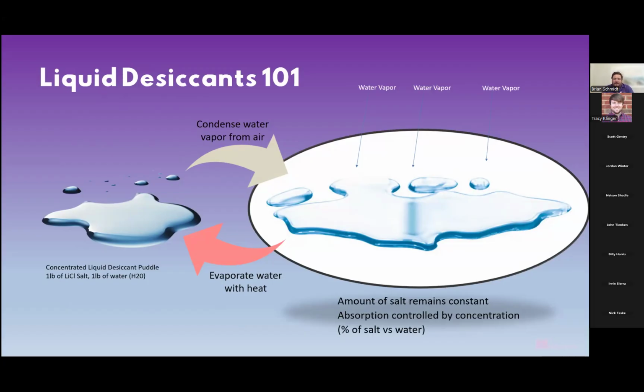Versus something like a solid desiccant that'll expand and contract and over time will break down. Liquid desiccants can thermally cycle infinitely. So you could even take a unit today, and let's say it lasts 15 years, whatever the lifespan is. You install a new unit to replace it. You could actually remove the liquid desiccant from the first unit, put it into the second unit, and continue to operate the system. As you'll see as we get further down in this discussion, they never need to top this stuff off. It's very, very salty water.